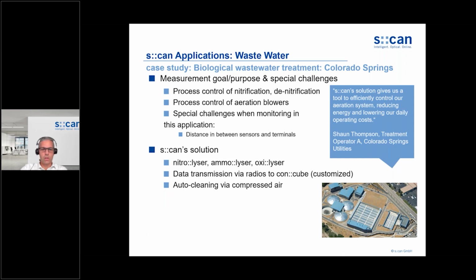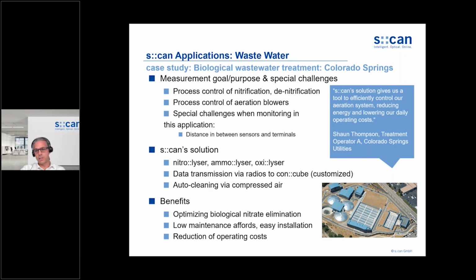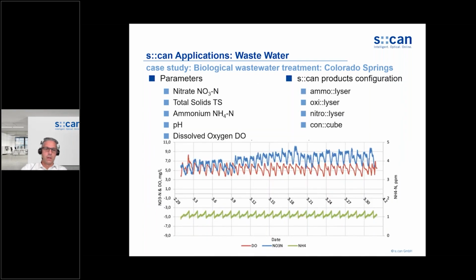Our solution here was nitrolyzer and ammolyzer and oxylyzer being submersed in the aeration tanks. The data transmission was done via radios to the concube. This was a customized solution. The auto cleaning, as typical in this application, via compressed air. The benefits for the customer were to optimize the nitrate elimination by the bugs, low maintenance efforts, and easy installation. And they reduced the operating costs significantly. The parameters monitored here were nitrate, solids, ammonium, pH, and dissolved oxygen.